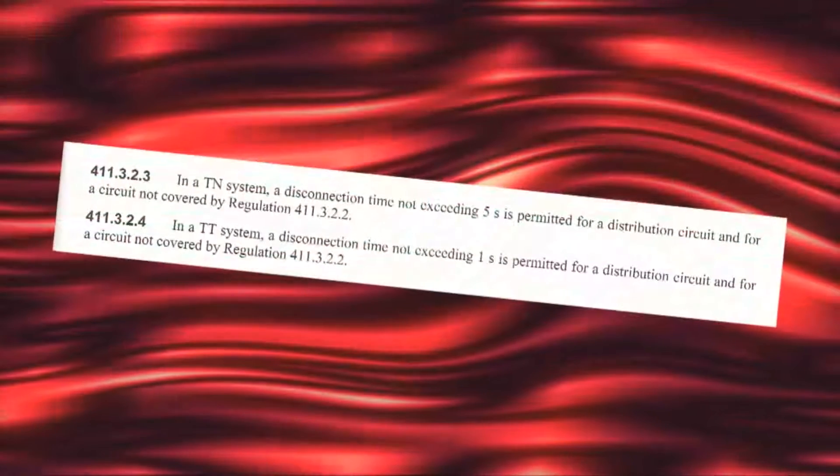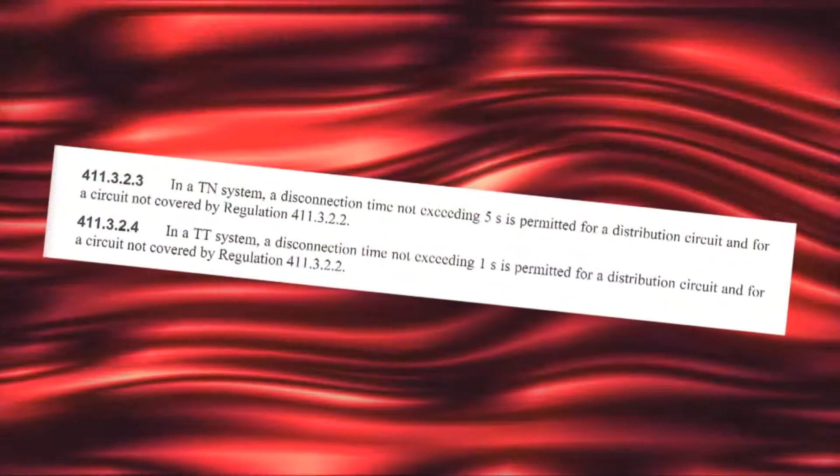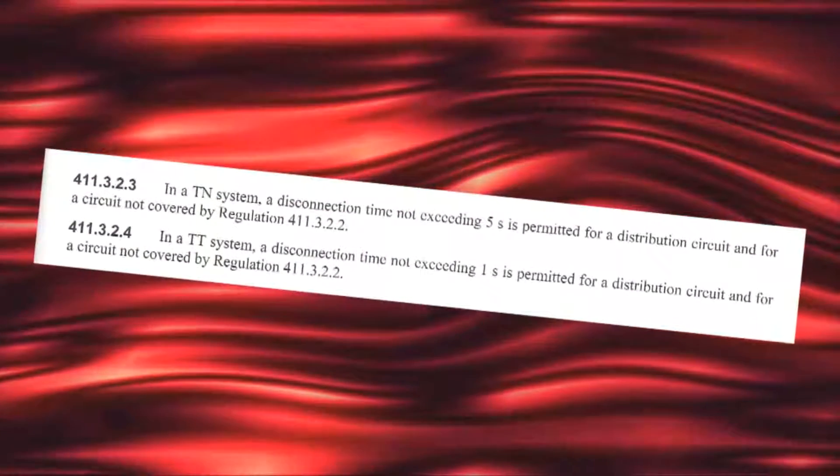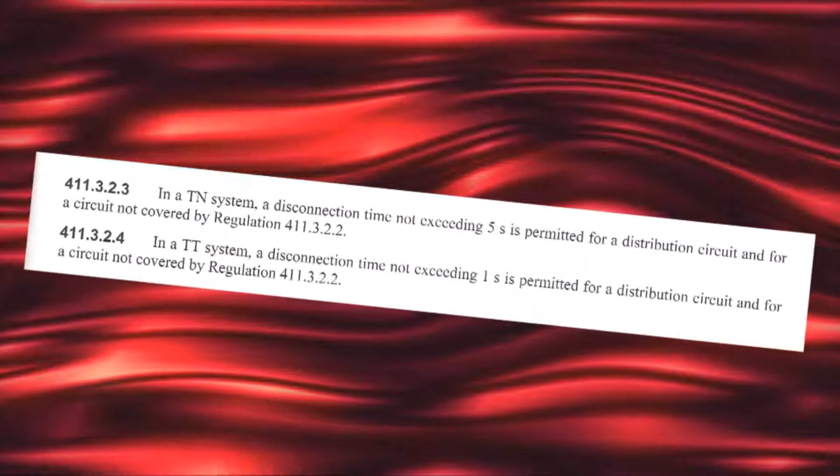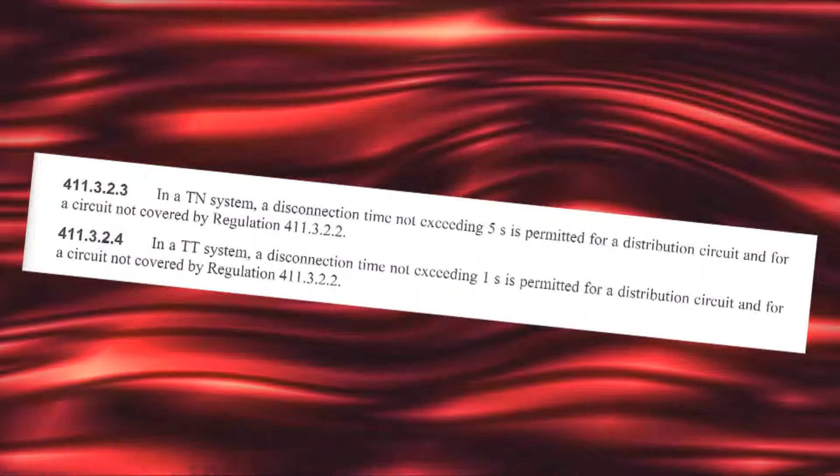For circuits rated at above 32 amps or distribution circuits, the regs do permit an increased disconnection time of 5 seconds on a TN and 1 second on a TT.